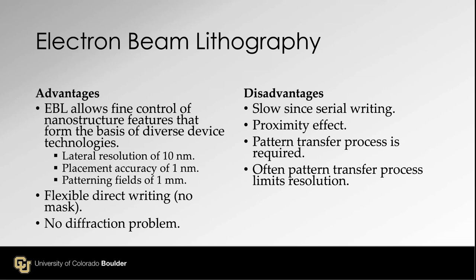Advantages of e-beam lithography: fine control of nanostructure, based on diverse device technologies, lateral resolution 10 nanometers, placement accuracy 1 nanometer, and patterning field size 1 millimeter. That's the limit. Flexible direct write, no mask required, no diffraction problem.